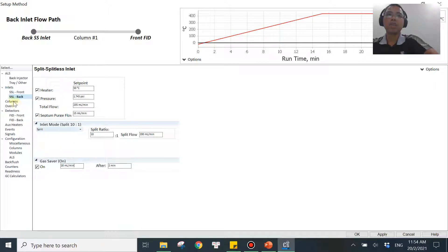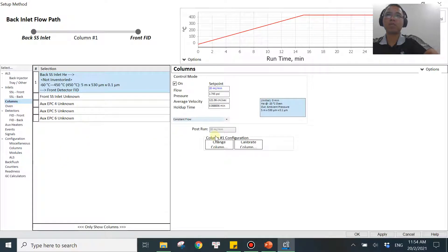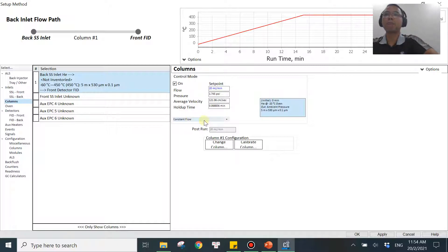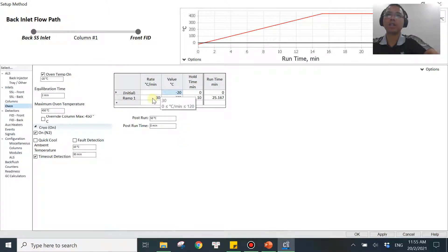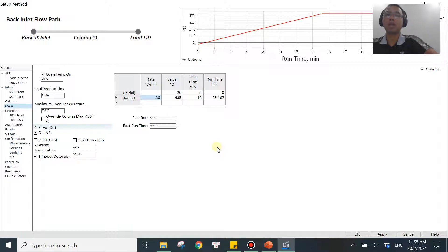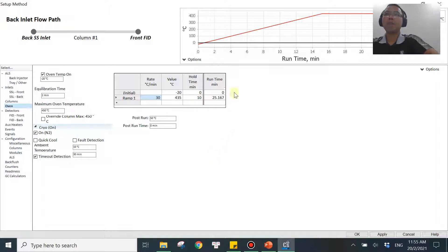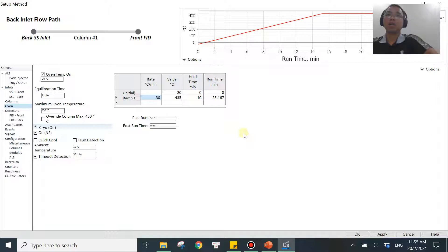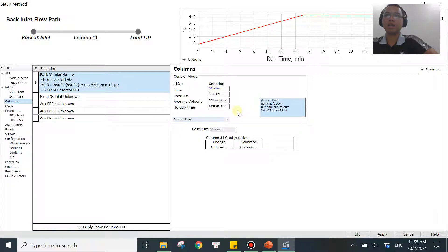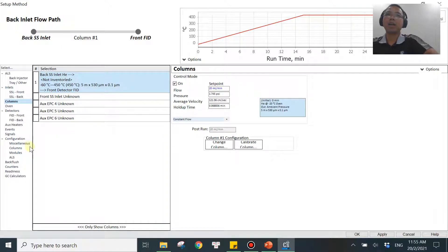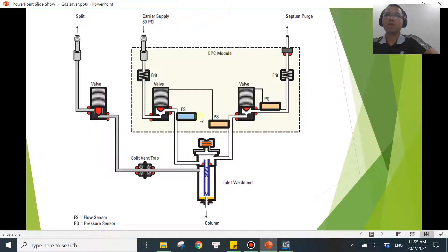So let's put in the scenario that you want to run a constant flow. Let's say your method, you have a constant flow rate for the column. But in the oven over here, you ramp up very, very quickly—let's say 30 or the ramp rate at 30 or even 35 or 40 degrees per minute. So that means you are ramping super, super fast, right? And as you know, if you are ramping the temperature of the oven super fast like that, the inlet pressure will have to increase to catch up, to compensate for the flow rate, because you define constant flow rate for your column. That means the inlet pressure will have to increase fast enough to maintain the constant flow rate over here.